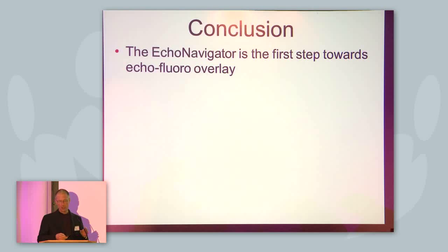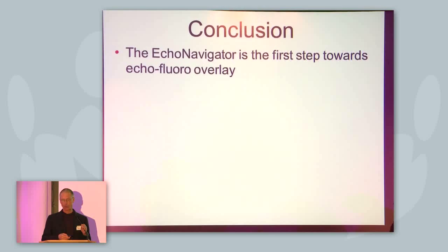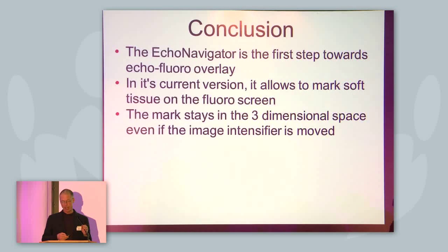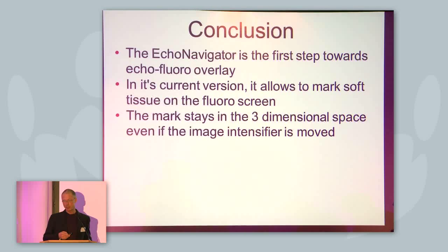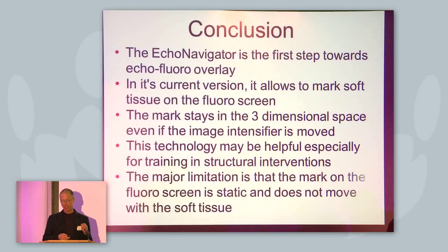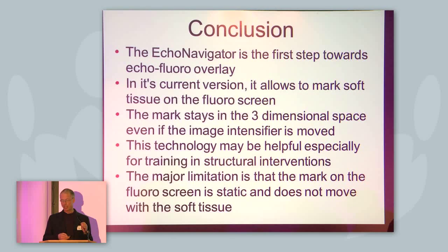In conclusion, the echo navigator is the first step towards echo-fluoro overlay. In its current version, it allows marking of soft tissue on the fluoro screen. The mark stays in the three-dimensional space even if the image intensifier is moved, rotated, zoomed in, or zoomed out. This technology may be especially helpful for training in structural interventions. The major limitation is that the mark on the fluoro screen is static and does not move with the soft tissue.